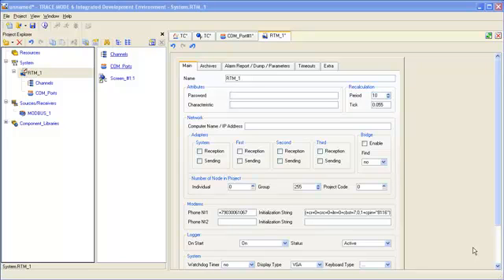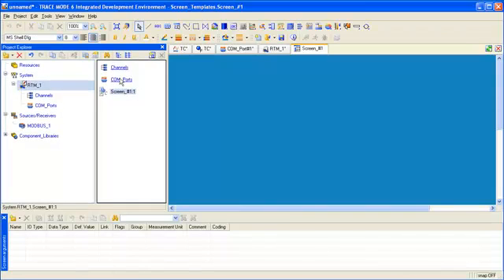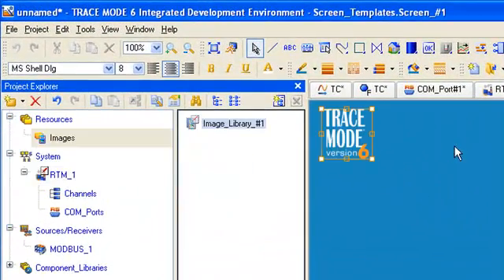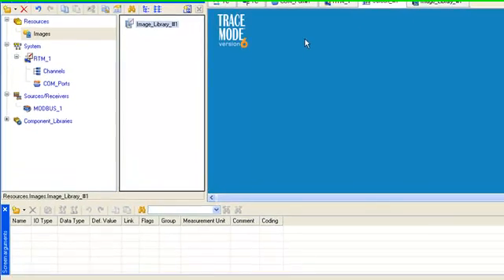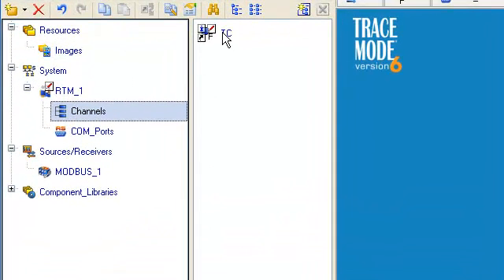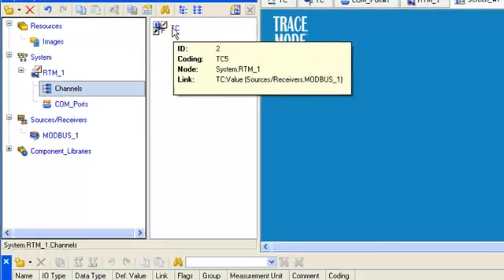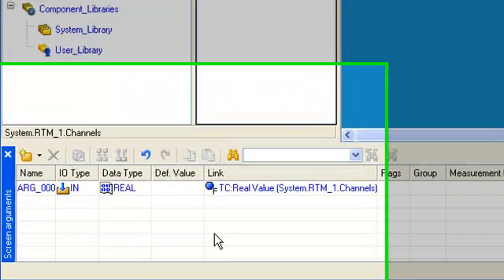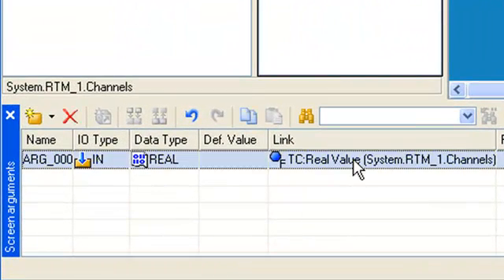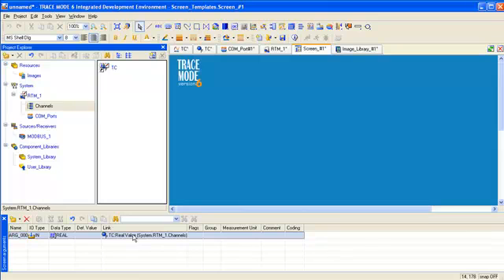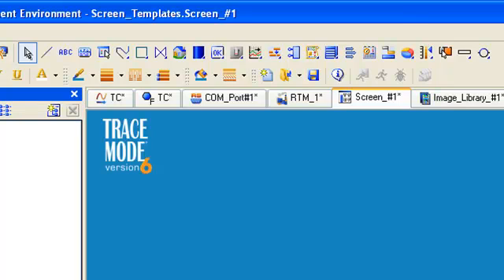Now, we'll view the real-time data from IO module on operator HMI. Let's open the component screen for editing and insert trace mode logo in the left upper corner. In order to show temperature value on our screen, we should drag and drop our channel with the name TC to the argument screen table. The temperature data are situated in the channel attribute real value. We will visualize the data by means of such graphic elements as gauge and trend.